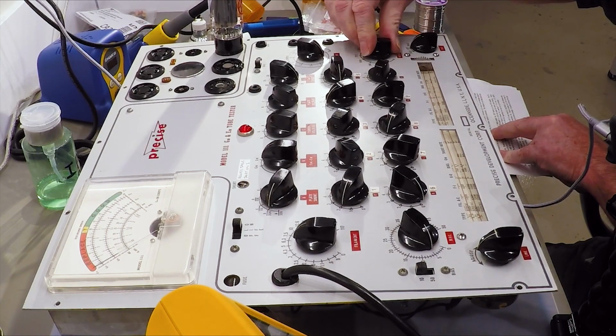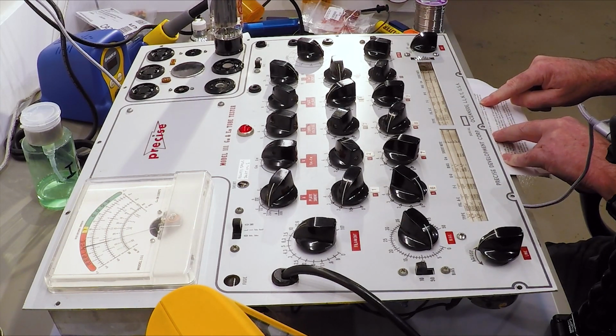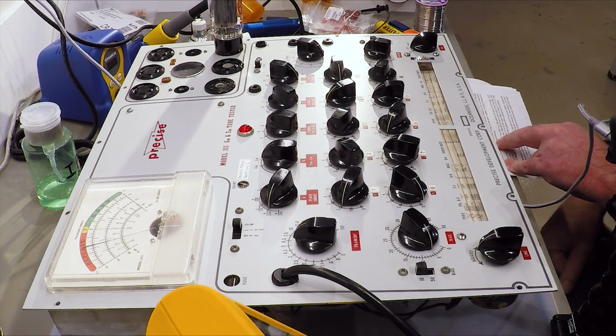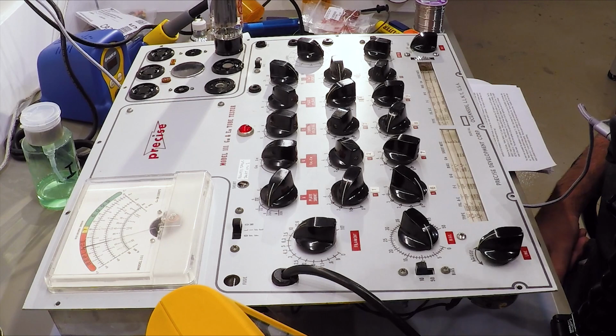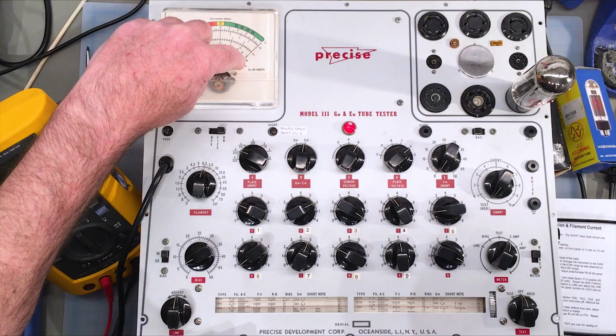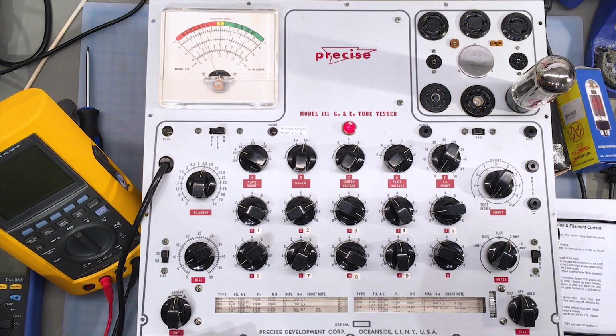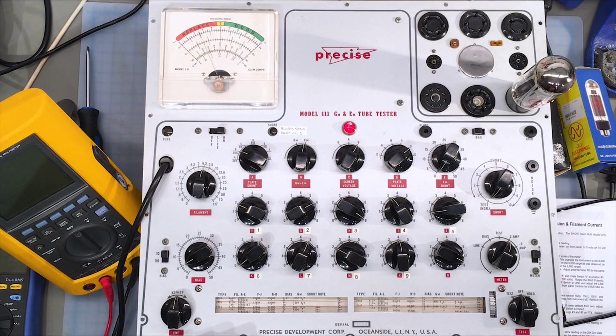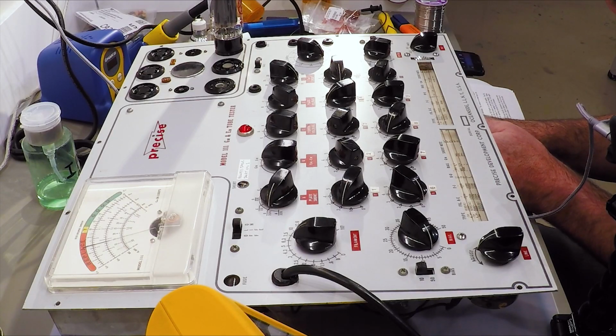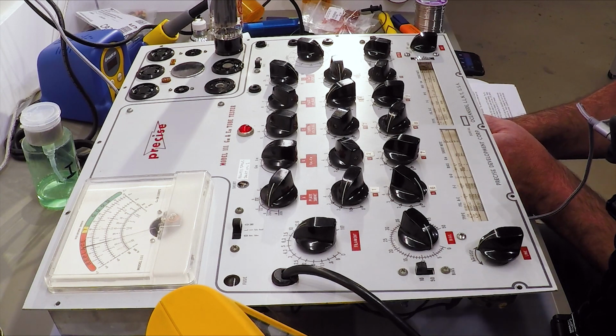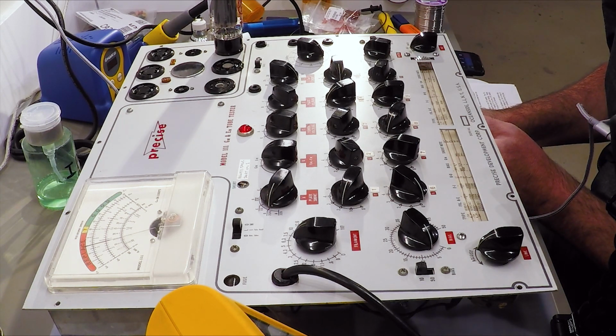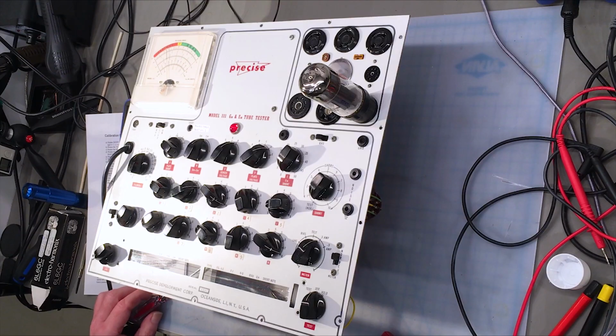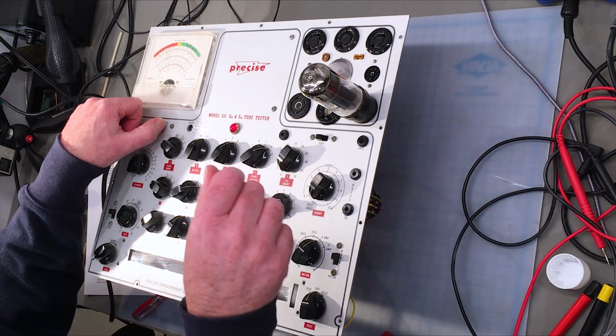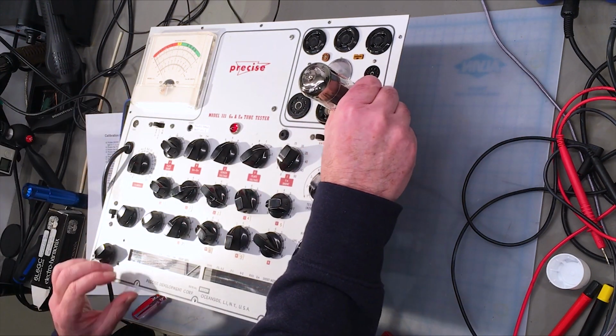We now turn this to 3 amps and adjust P12 for a reading of 0.9 on the 3 filament amp scale, and that is the second bottom scale. And we're currently at approximately 0.85. So P12 is in the bottom right-hand corner, and again, using a screwdriver, just adjusting this ever so slightly, getting us to 0.9 amps. And that's that. Now we are to remove this tube. I'll just turn this off for a moment.